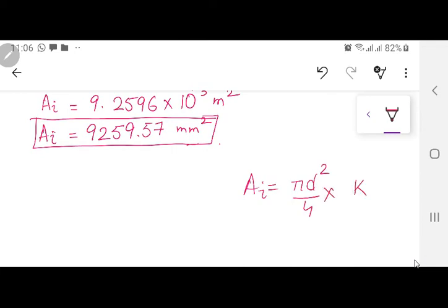What was that K factor? That K factor was the total area that was being covered inside the circle, whatever step you were assuming. Now if you see on this table, from the 4th step up till the 11th step, you have been given the data. For example, for a 6-step core, the approximate value of K is 0.92. For 7th step, this is 0.925. For 8 steps, it's continuously going on.